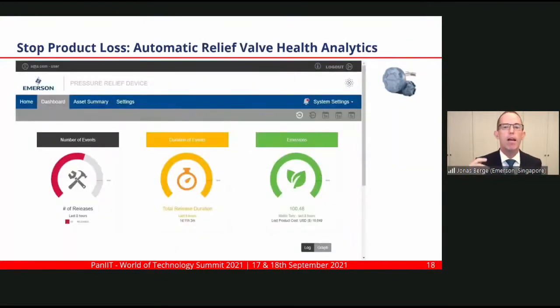Similarly, relief valves are manually inspected today, maybe yearly. So plants put in automation for this - the sensor and the analytics. You know, sensor is not enough, analytics is not enough, you need both. So now if the relief valve is releasing, you get a precise timestamp of that, and you can correlate it to process events and make changes to prevent releases in the future. Worst case, if the relief valve is stuck open, you get to see that too.